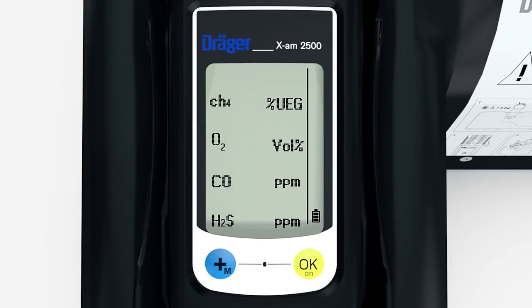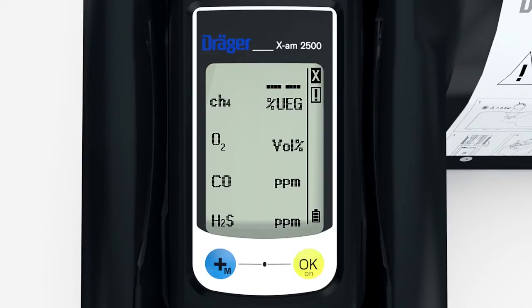If a functional test does not take place correctly, a channel error is shown for the sensor or sensors. The device will have to be calibrated and possibly repaired.